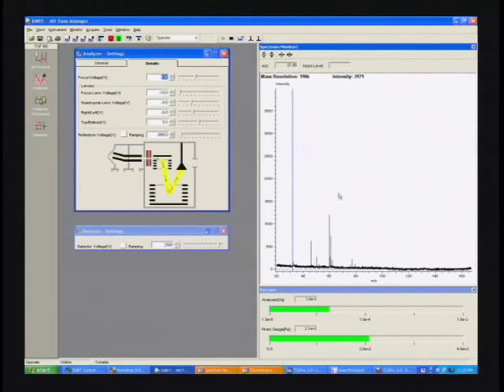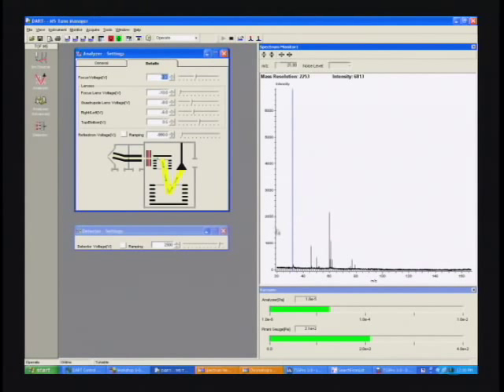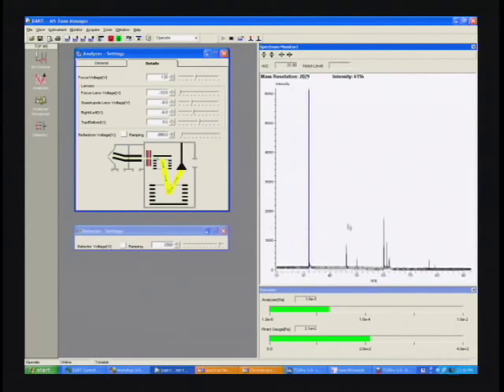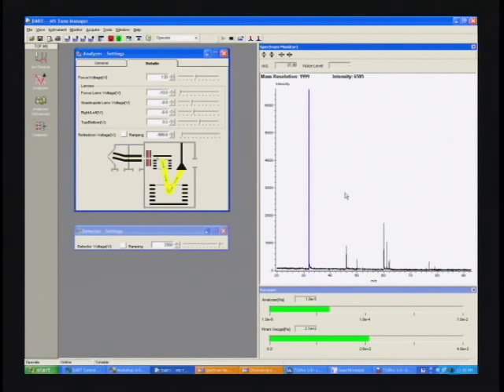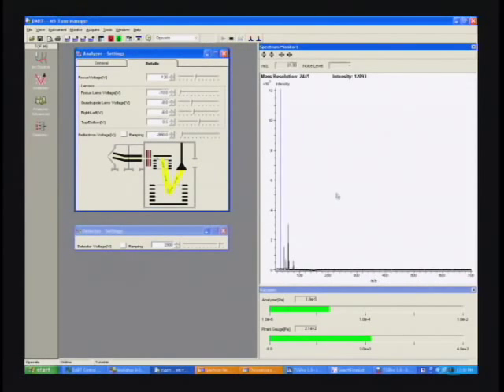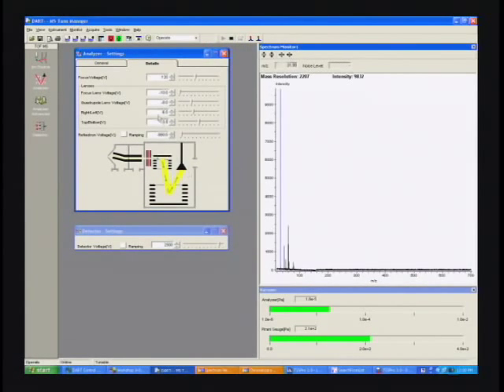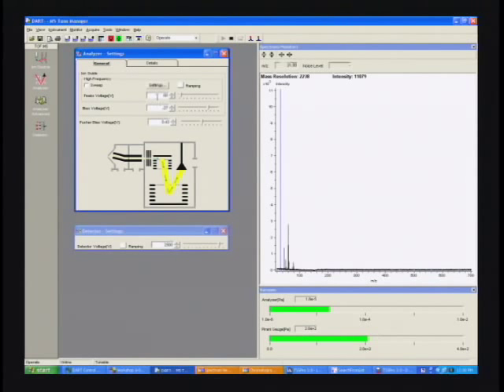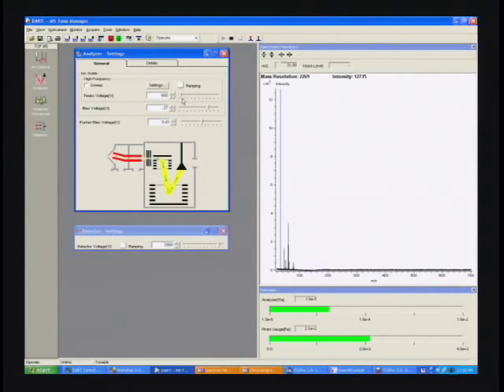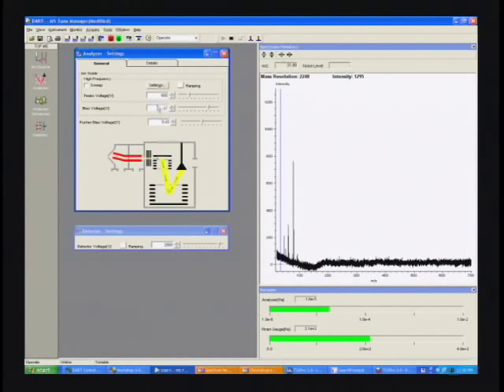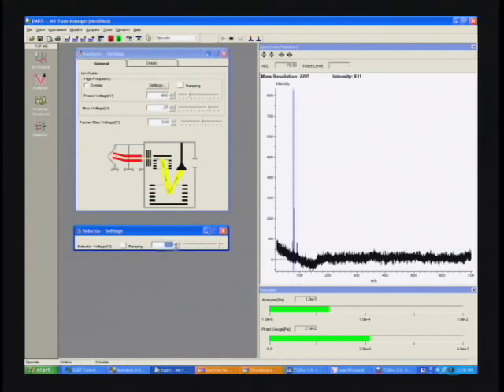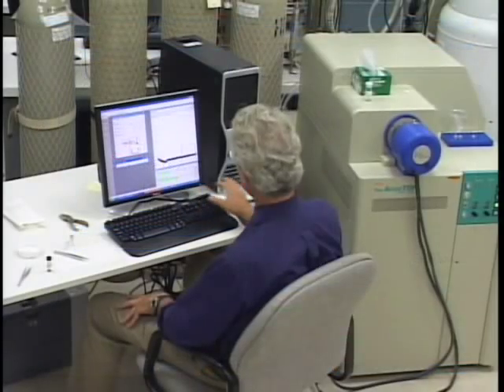Just a little bit longer. This is a typical negative ion dart background. It's mostly just oxygen and some water and carbon dioxide clusters. So there we go. That's looking good. Now we'll set the analyzer voltage a little higher so we don't have to look at all those low mass peaks. And we'll open up a data file and save the results. I'll raise the multiplier a little bit.